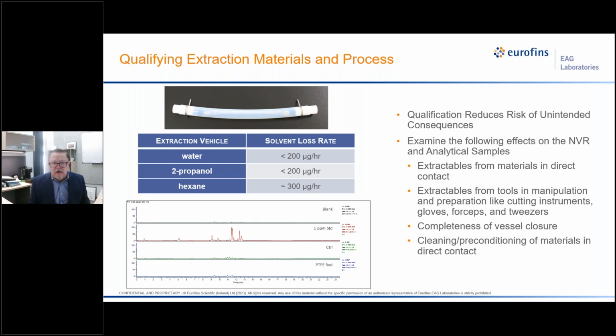And in those cases where there are significant contributions, you need to really be concerned about it, because in some cases those contributions, in the case of LCMS, for example, could lead to ion suppression and an inability to adequately detect or quantify analytes, extractables that might be in that same region. You could subtract out the contributions from the device, from the extraction vessels, but ultimately they could have a significant impact on the quality of your work.